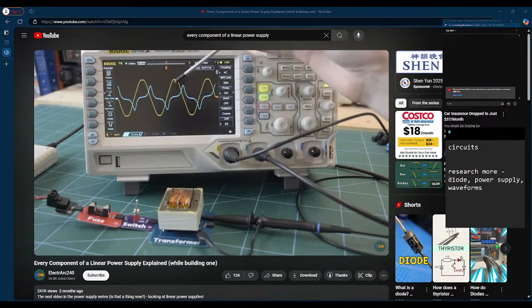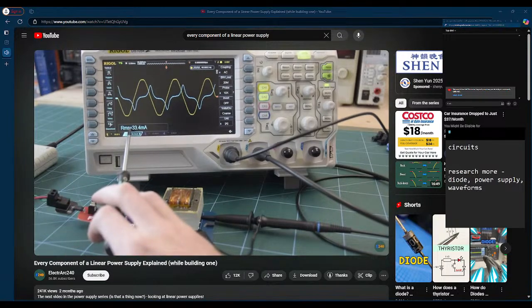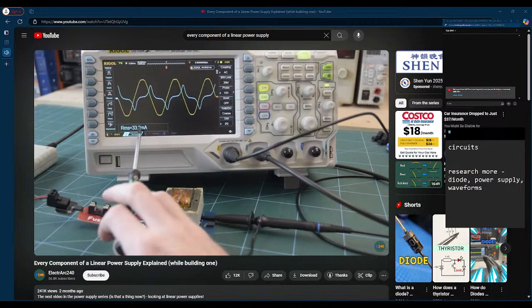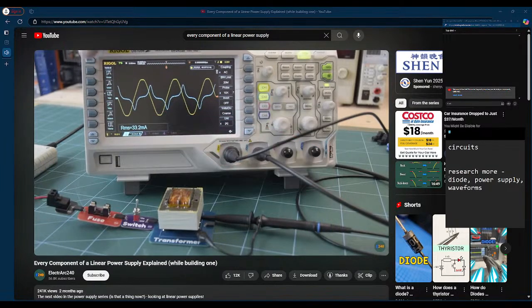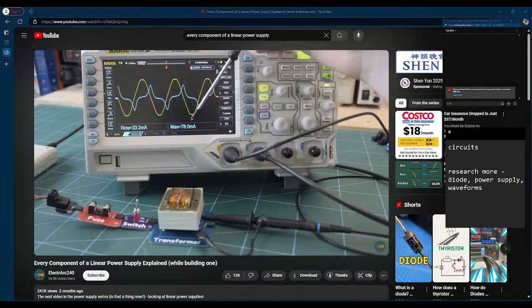So you might find that at 230 volts, this blue waveform is a little bit nicer. And you can see here I've added a measurement for the RMS current, and it says 33 milliamps, which is about the same as what we got from our clamp meter that we put on earlier. Although we can also see that the maximum or peak current is almost 80 milliamps because of this saturation.